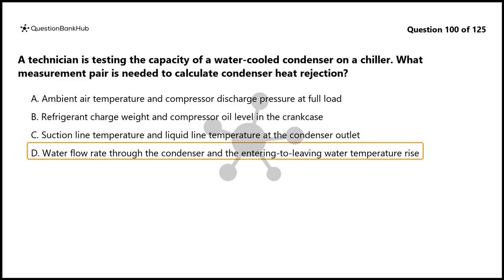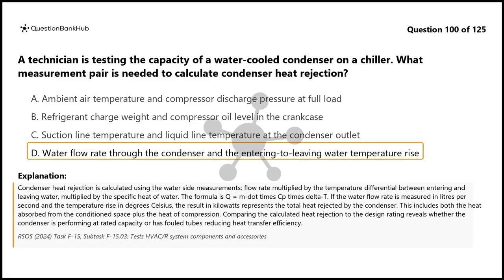The correct answer is D. Condenser heat rejection is calculated using the water side measurements, flow rate multiplied by the temperature differential between entering and leaving water, multiplied by the specific heat of water. The formula is Q equals m dot times Cp times delta T.